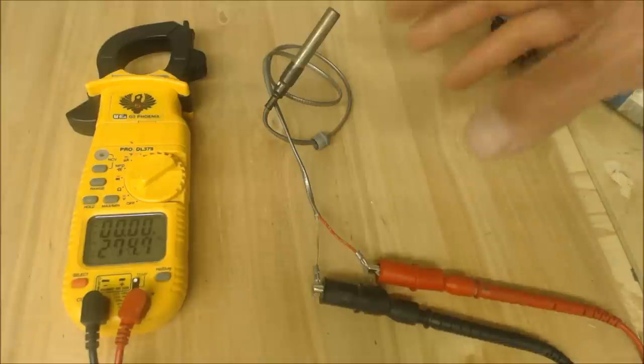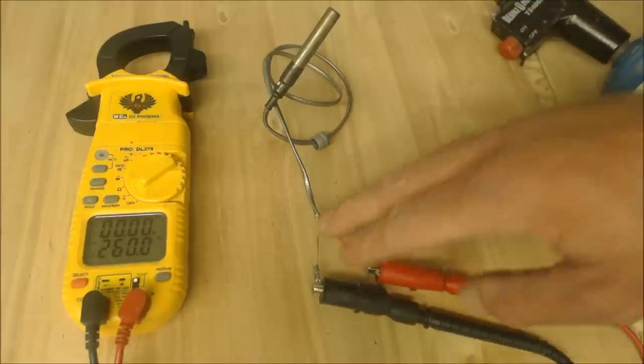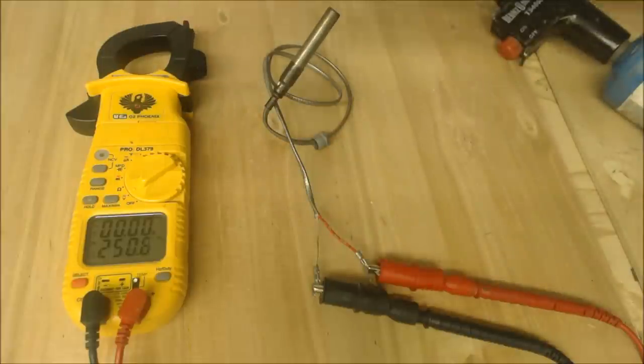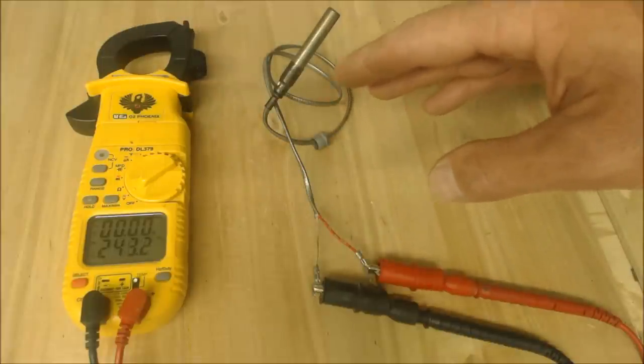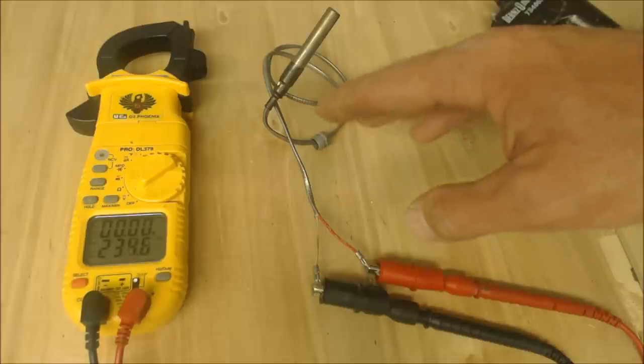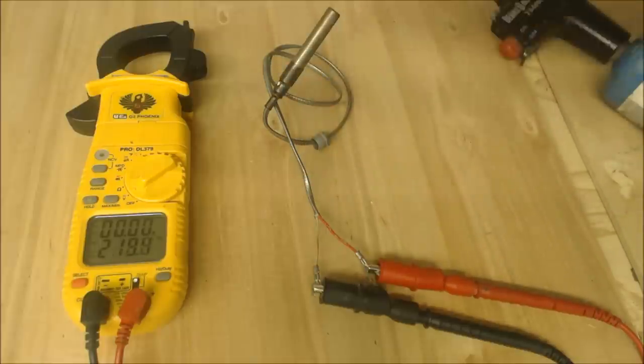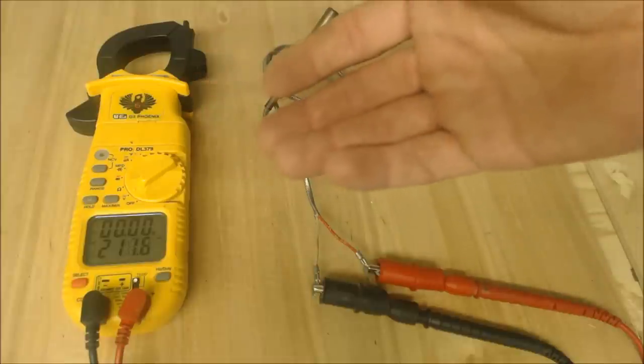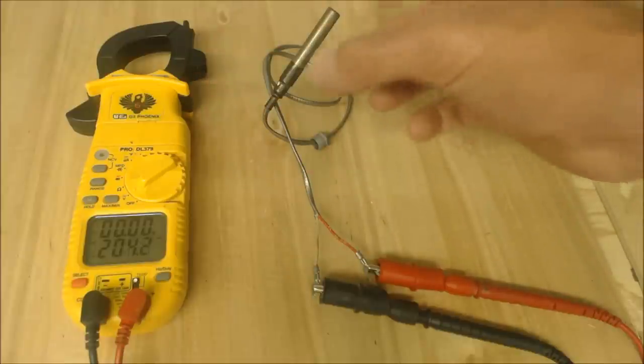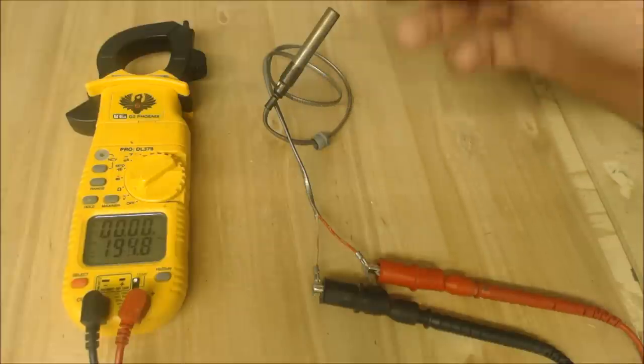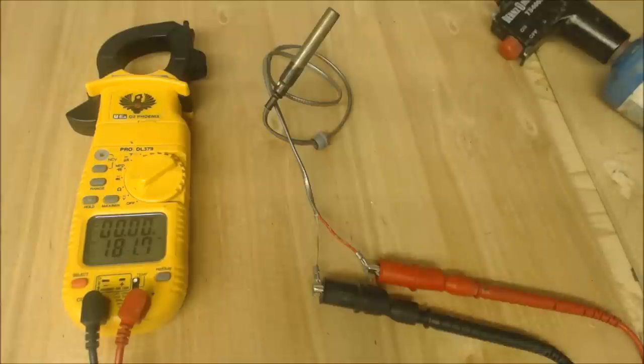So if this was connected to the gas valve and the gas is flowing through, what you're looking for is about at least 190 millivolts DC. So say your gas valve is clicking but the gas isn't going through, maybe you're not supplying enough power, millivolts DC to actually allow that gas valve to actually open for the gas to flow through.